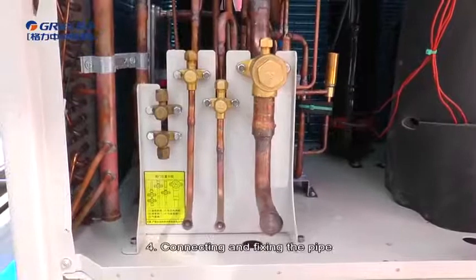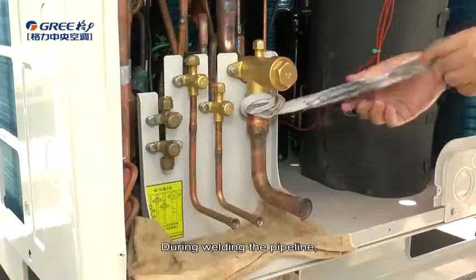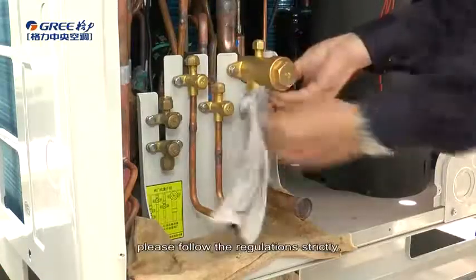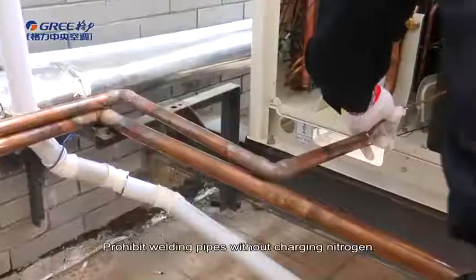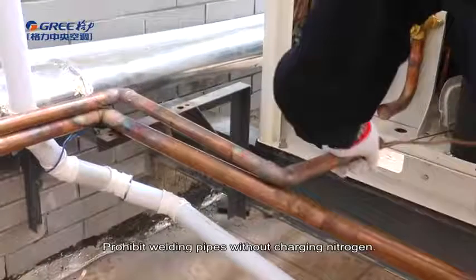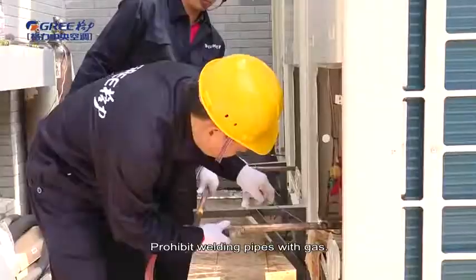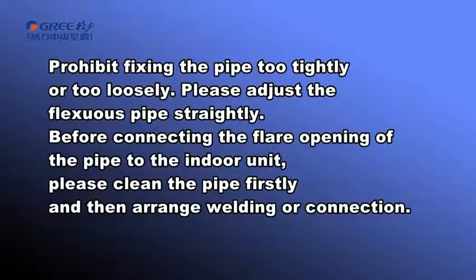Fourth, connecting and fixing the pipe. During welding the pipeline, please follow the regulations strictly. Prohibit welding pipes without charging nitrogen. Prohibit welding pipes with gas. Prohibit fixing the pipe too tightly or too loosely. Please adjust the flexuous pipe straightly. Before connecting the flare opening of the pipe to the indoor unit, please clean the pipe first and then arrange welding or connection.